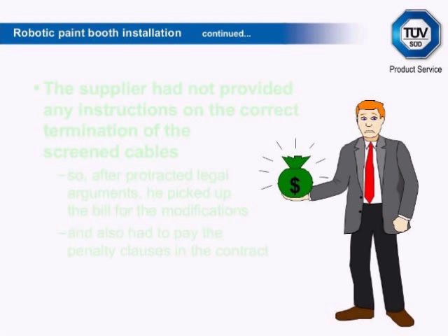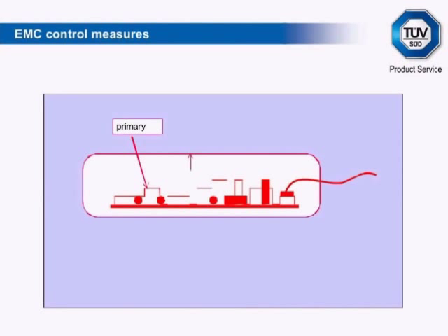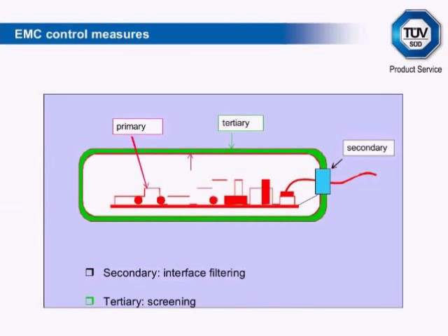EMC control can be applied at three levels: primary, secondary, and tertiary. Control at the primary level involves circuit design measures such as decoupling, balanced configurations, bandwidth and speed limitation, and also board layer and grounding. For some low-performance circuits, especially those which have no connecting cables, such measures may be sufficient in themselves. At the secondary level, the interference between the internal circuitry and external cables is invariably a major route for interference in both directions, and for some products — particularly where the circuit design has been frozen — all the control may have to be applied by filtering at these interfaces.